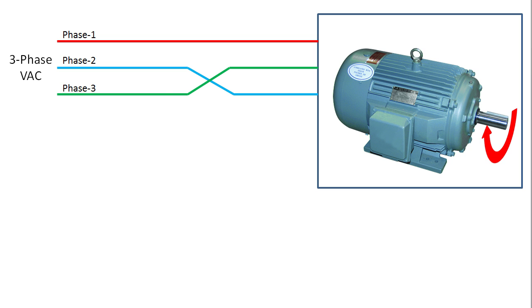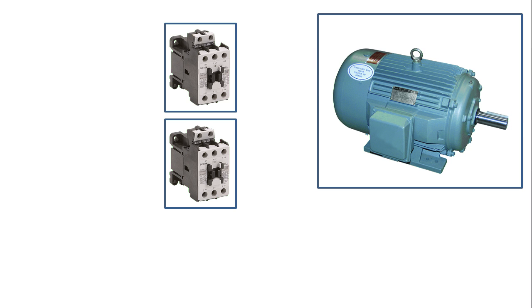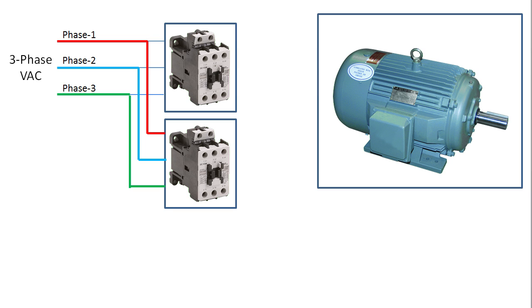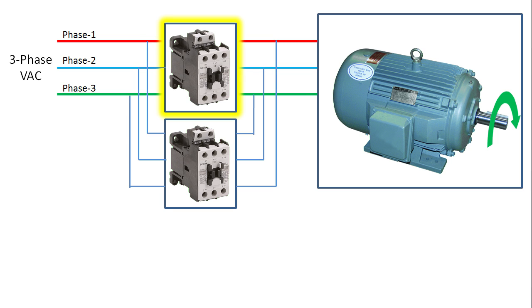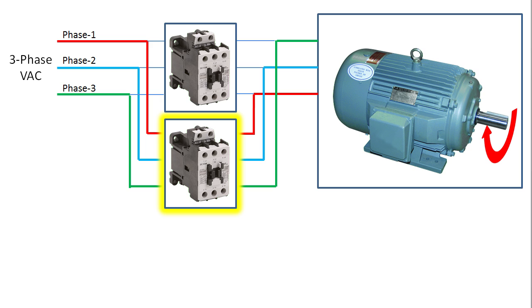To reverse a three phase motor using contactors you just run one set of wires straight through one contactor and a parallel set of wires through another contactor where you swap one set of wires. When this contactor is engaged the motor turns one way and when this contactor is engaged it rotates the other direction.